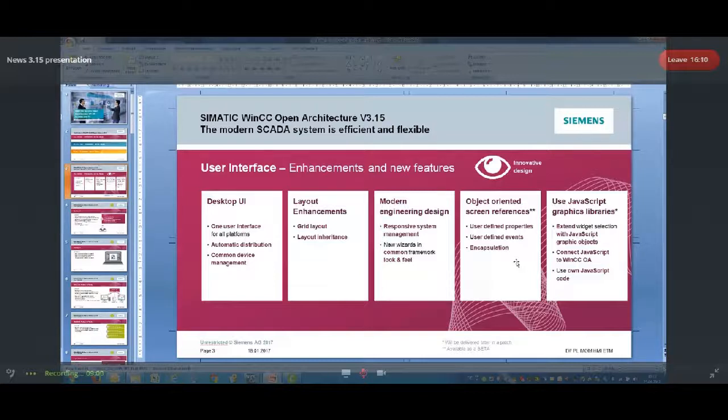And in this JavaScript code, you can use the process image of WinCC OA, so all data points, everything. You can do dpConnect, you can do dpGet, dpSet, dpGetPeriod. So you can interact with your process data directly from JavaScript code on a web page that is viewed in the WebView widget. And the use case is nice graphics, dashboarding, and other things aside from the trend.